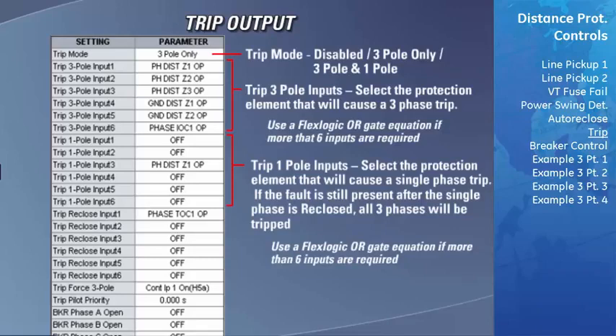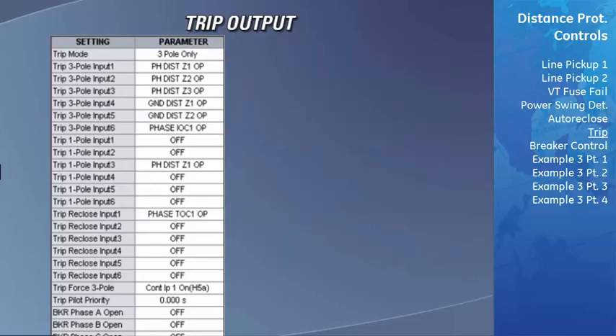If single-phase tripping is configured and a single phase is tripped upon detecting a fault, this single phase will automatically be reclosed by the D60. If the fault is still present after this reclosing, all 3 phases will immediately be tripped. If you require the ability of selecting more than 6 inputs to cause a single phase trip, you will need to create a flex logic equation where all of those additional inputs will be ORed together and then assign that virtual output to this list.